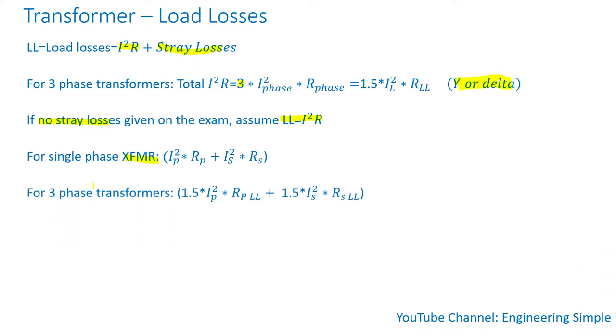For three-phase transformers, the total I squared R is 1.5 times the line current of the primary winding squared times the line-to-line resistance of the primary, plus 1.5 times the line current of the secondary winding squared times the line-to-line resistance of the secondary winding.